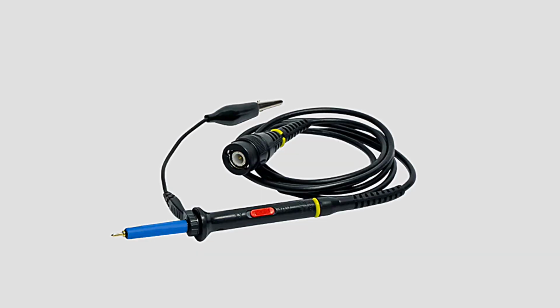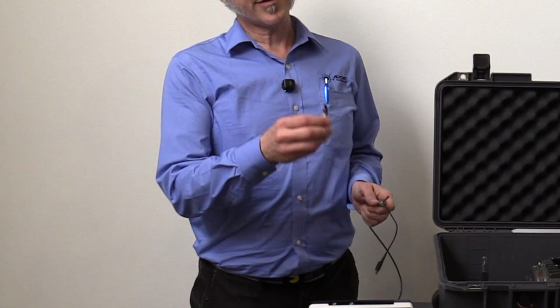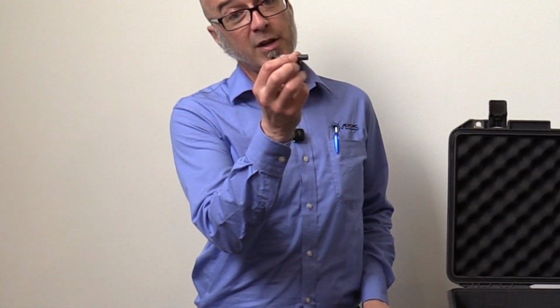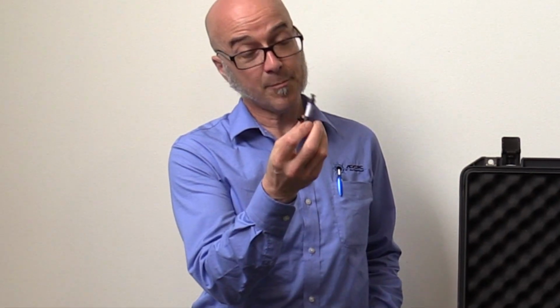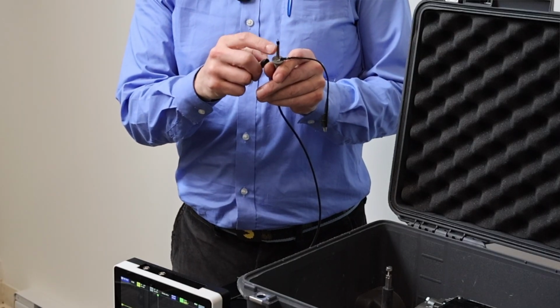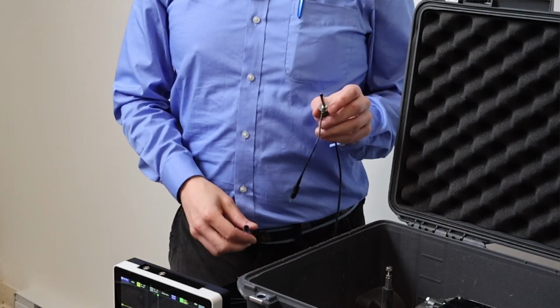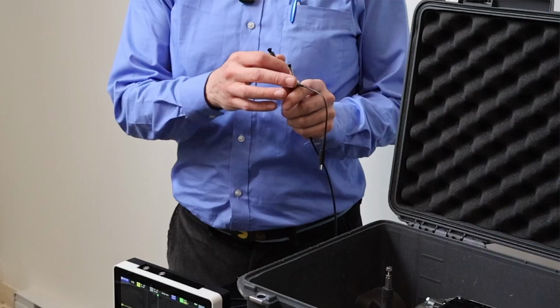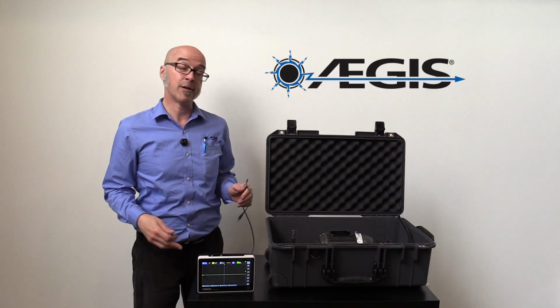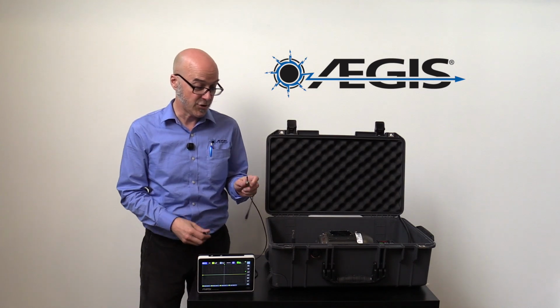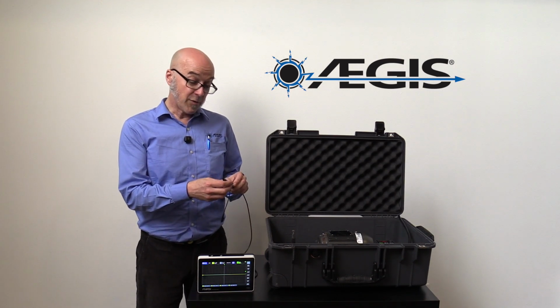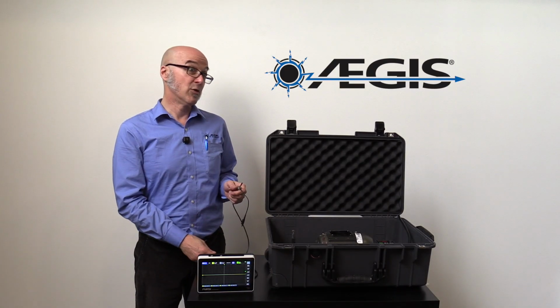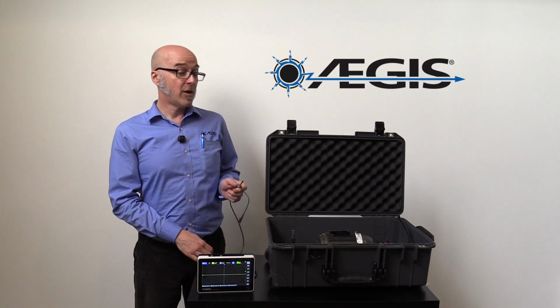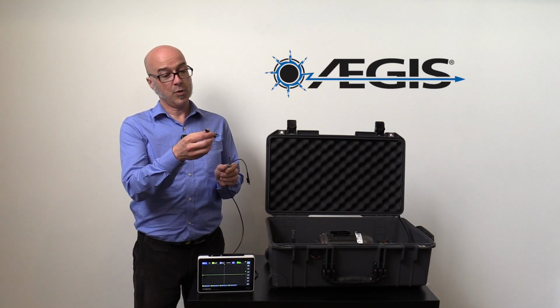Electrostatic Technology actually sells an Aegis probe that is much like this, but it has heat shrink over the ground barrel. And the reason for that is in case there are any loose fibers or stray fibers inside one of our shaft voltage testing tips. Well, if there are loose fibers and they touch the ground barrel, then you're going to get no signal. But most of the time, it's fine not to have this heat shrunk. It's just belt and suspenders if you want to heat shrink it. If there is a problem, you find out when you go to measure and you get 0 voltage for everything you try to measure. With all that said, let's put on a probe tip.